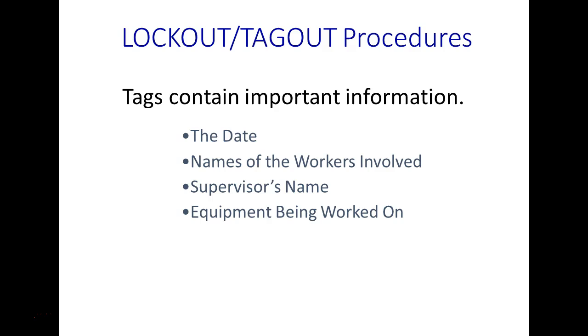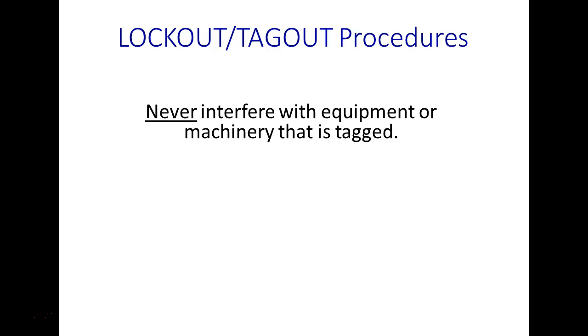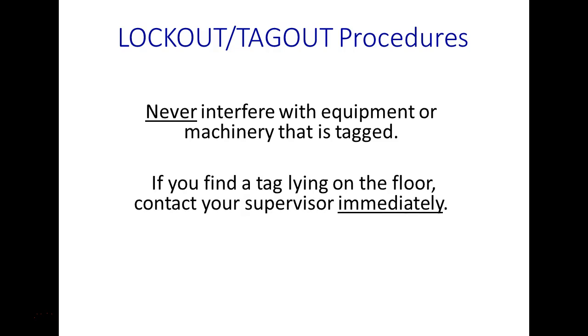And of course they make them bigger. These are just the ones that we have here. It's pretty obvious how they work. A lot of the disconnects out of U.S. Steel had multiple locks on them, about 6 or so. And that covered most situations on the disconnects themselves. Are we okay? Never interfere with equipment or machinery that is tagged. If you find a tag lying on the floor, contact your supervisor. Which makes sense. Tags are usually made out of paper. You know what happens? People accidentally hit them and they'll tear off.